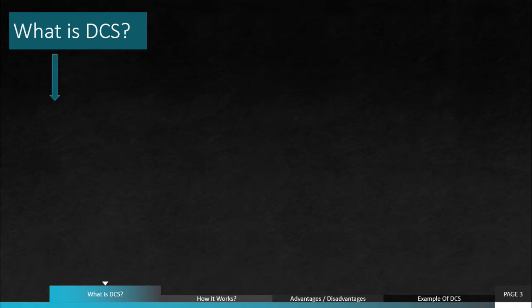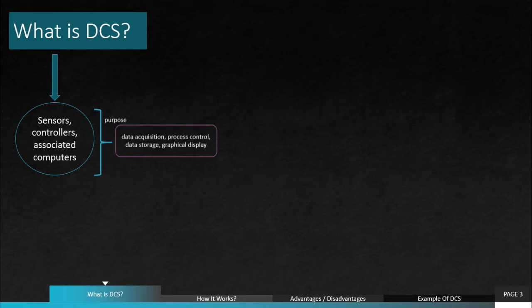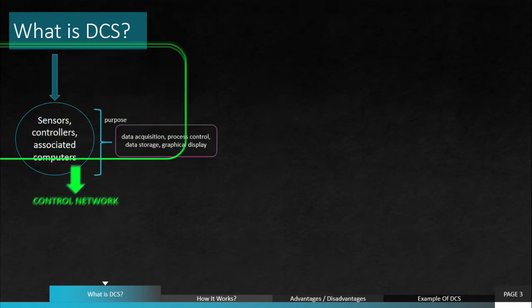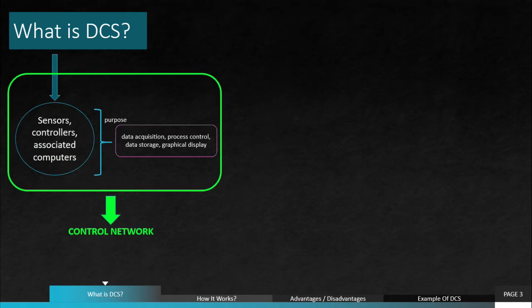Distributed control system is a system of sensors, controllers, and associated computers that are distributed throughout the plant. Each of these elements serves a unique purpose, such as data acquisition, process control, as well as data storage and graphical display. These individual elements communicate with a centralized computer through the plant's local area network, often referred to as a control network. As the central brain of the plant, the DCS makes automated decisions based on the production trend. It sees them in real time throughout the plant.